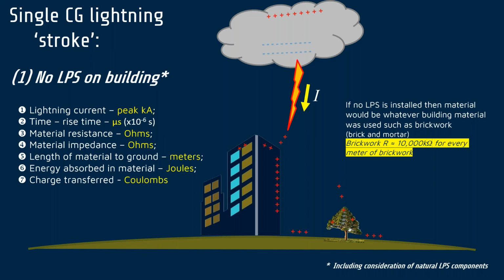So, bringing us back to this building, without any metallic means by which the charge can be transferred to ground with the least path of resistance, we are forcing 10,000 amps and more into this brickwork. Now, very quickly, somebody will say, "Hold on, it's not 10,000 amps. It's 10,000 amps rising at 5 microseconds and then falling away at 100 microseconds. So at 200 microseconds, it's come and gone. So it's not 10,000 amps." So at the moment that it's 10,000 amps, all the charge that is in the cloud is going to ground.